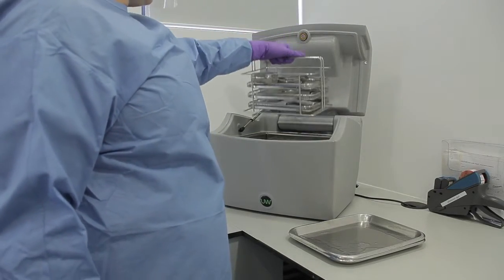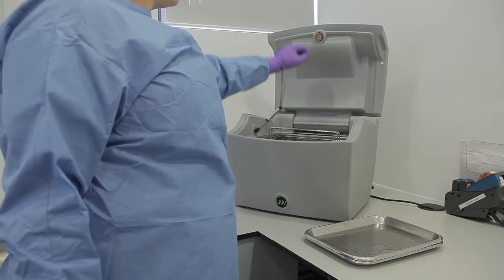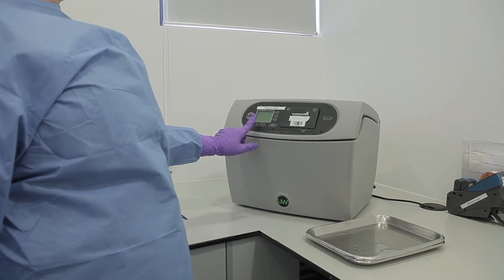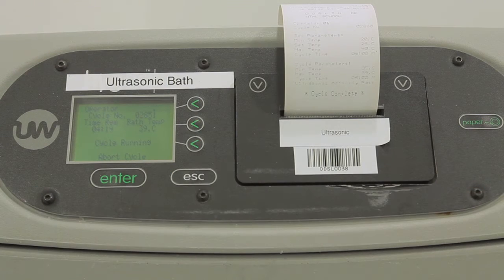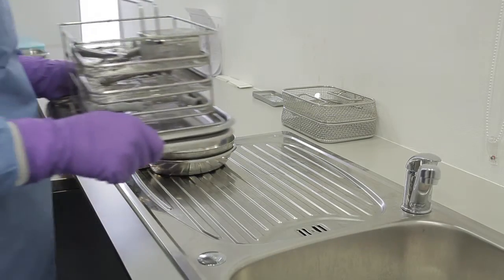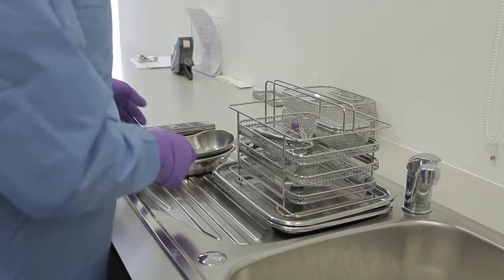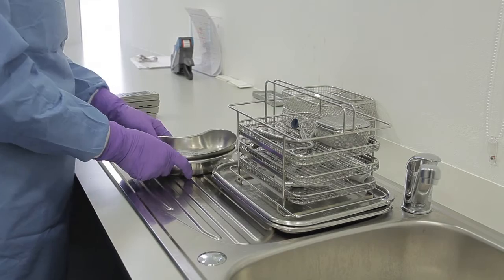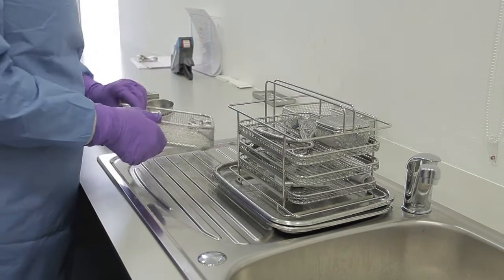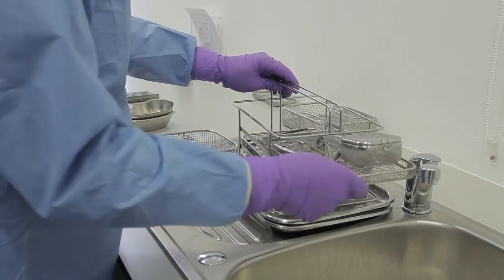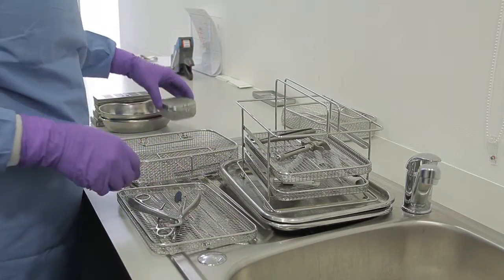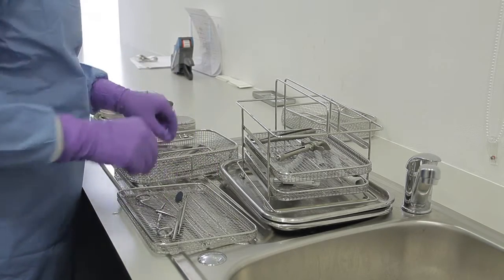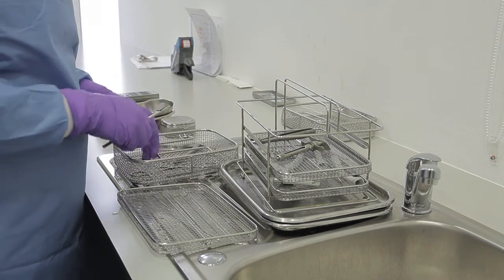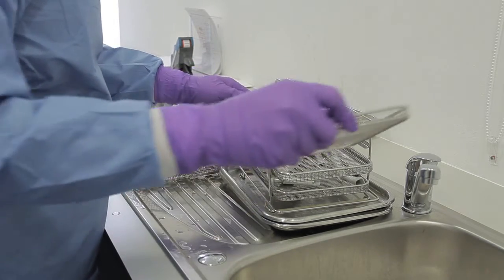This ultrasonic bath operates for a total of 6 minutes. The temperature range is a minimum of 20 degrees centigrade and reaches a maximum temperature of 40 degrees centigrade. These are the key parameters for checking the graph and releasing the instruments to the next step of the decontamination life cycle. This ultrasonic bath uses an enzymatic-based solution which helps to break down and loosen organic contaminants from RIMD. The RIMD that are removed from the ultrasonic bath are still contaminated. When the cycle is finished, the dental healthcare worker removes the instrument trays from the ultrasonic bath, then places them on a metal tray to reduce spread of contamination caused by dripping water. The trays containing the RIMD are transferred to the washer disinfector holding area.